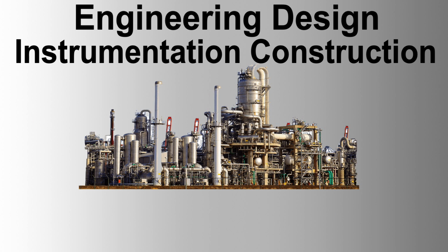Piping and tubing runs shall be adequately supported and fixed at distances not exceeding those in the following table. Tubing, 3/8 inch OD, 0.75 meters; 1/2 inch OD, 1.5 meters; 1/4 inch OD, 0.5 meters. Capillaries of filled systems shall be run independently of all other lines and shall be continuously supported using mild steel angle with clips at 0.5 meter intervals. Where pipes are led through apertures made in the body of the tray, the edges of these apertures shall be lined with lead or plastic. Where steel support is considered sufficient, the parts shall be properly primed and painted.